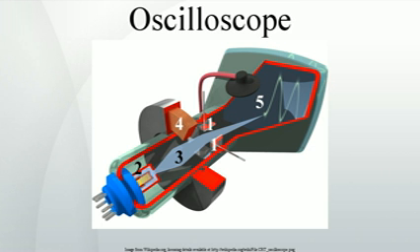The trigger event is usually the input waveform reaching some user-specified threshold voltage, trigger level, in the specified direction, going positive or going negative, trigger polarity. In some cases, variable hold-off time can be really useful to make the sweep ignore interfering triggers that occur before the events one wants to observe. In the case of repetitive, but quite complex waveforms, variable hold-off can create a stable display that cannot otherwise practically be obtained.